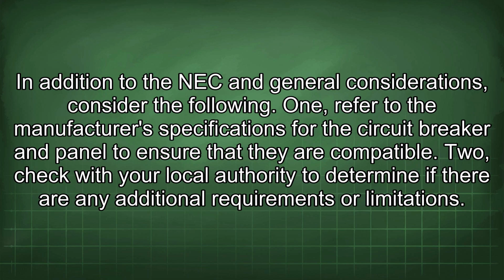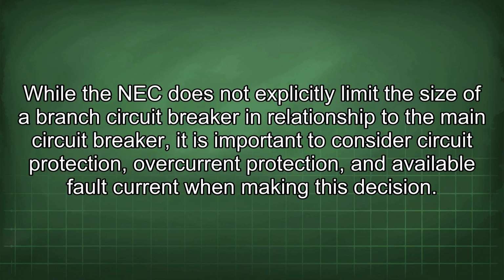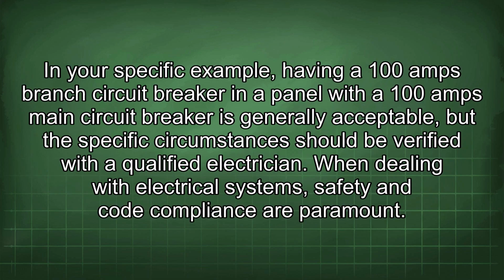In addition to the NEC and general considerations, consider the following. 1. Refer to the manufacturer's specifications for the circuit breaker and panel to ensure that they are compatible. 2. Check with your local authority to determine if there are any additional requirements or limitations. While the NEC does not explicitly limit the size of a branch circuit breaker in relationship to the main circuit breaker, it is important to consider circuit protection, overcurrent protection, and available fault current when making this decision. In your specific example, having a 100 amps branch circuit breaker in a panel with a 100 amps main circuit breaker is generally acceptable, but the specific circumstances should be verified with a qualified electrician.